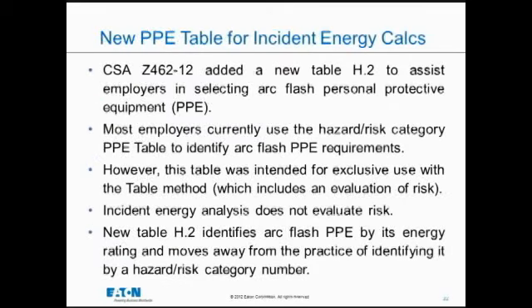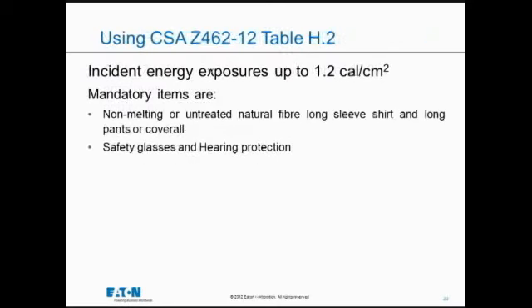It's just describing the fact that this table is supposed to be used. You cannot use hazard risk category anymore. And they break it down into three bins or three levels. Up to 1.2 calories, that's the level where human skin can take. We can take up to 1.2 calories and not get a second-degree burn. We can still wear flammable clothing. It's still allowed. Non-melting, natural fiber clothing, and that's generally cotton, wool, silk, hemp, bamboo, rayon. Those are natural fibers that will catch on fire when exposed to arc flash hazard. And the number where people generally say we're going to catch on fire is around 2 calories for, let's say, jean weight fabric.